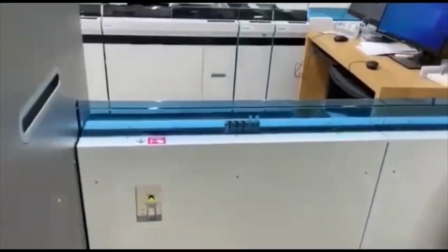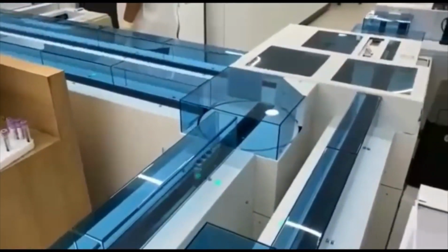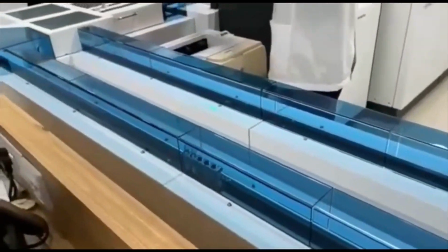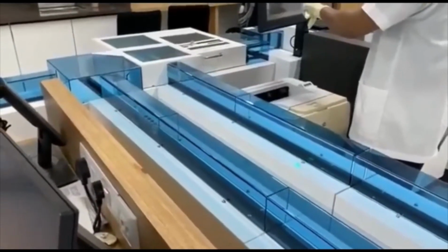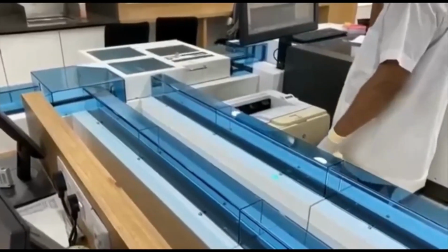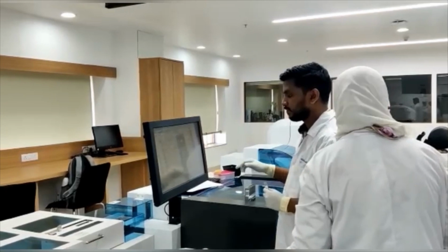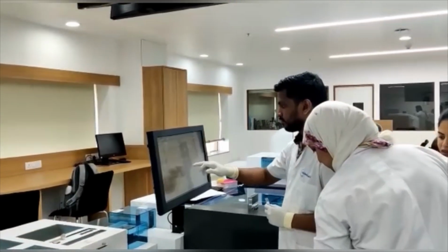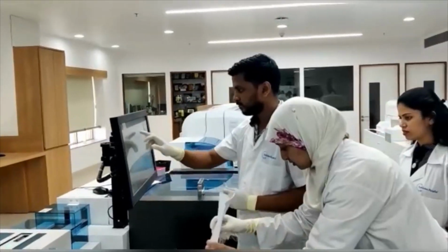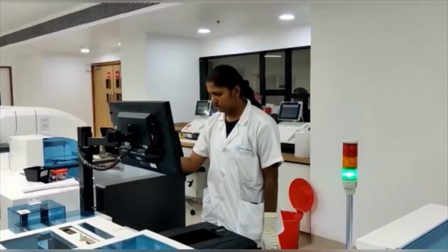After that, samples are sent to the analyzers for analysis of biochemistry, immunology, hematology and other tests. After analysis is done, samples come back to the output module, where for pending tests there is a recursive workflow, then rerun, recheck and archiving.